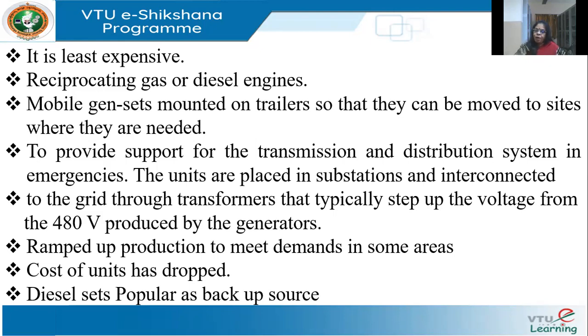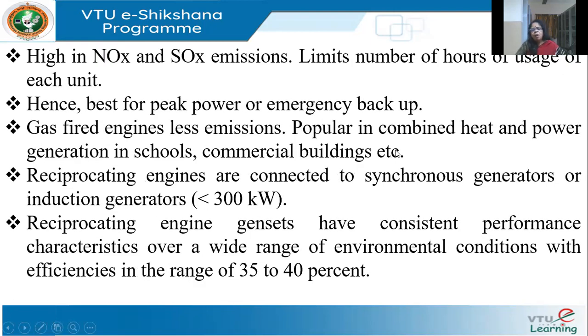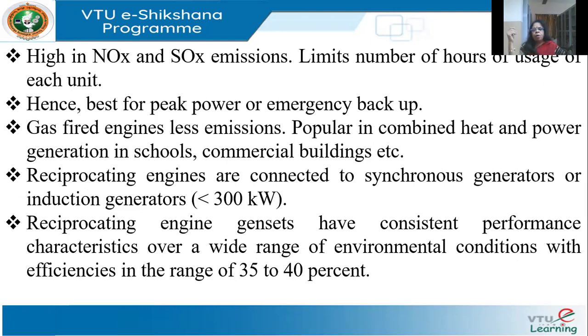Diesel gensets have become a very popular backup source. However, they are very high in nitrous oxide and sulfuric oxide emissions, so their hours of usage are limited — you can't use them 24/7 throughout the year. This is not a renewable source of DG because you are using diesel or gas. Because of their limited hours of usage, it's difficult to use these plants for base load — they are preferred for peak load or emergency backup.